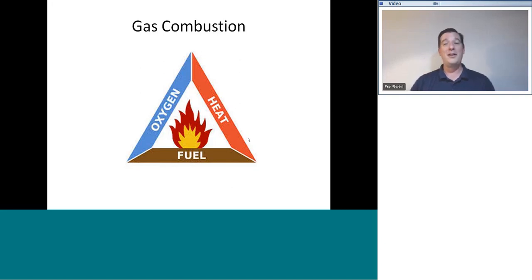When we want to start a fire and maintain a fire, these are the things that we need. This is critically important. When I work with service technicians, both junior technicians and very experienced technicians alike, and they're having a problem figuring out a gas heating issue, one of those stumpers, one of those difficult ones where you've got to go back two or three times to figure it out, it almost always comes down to one of these three things. So this is very basic, but it's very important. It's very easy to overlook in the field. So remember that when you're stumped, chances are you're going to be looking for a problem with one of these things. Your oxygen supply isn't good enough, you have a heat issue, or you have a fuel issue.